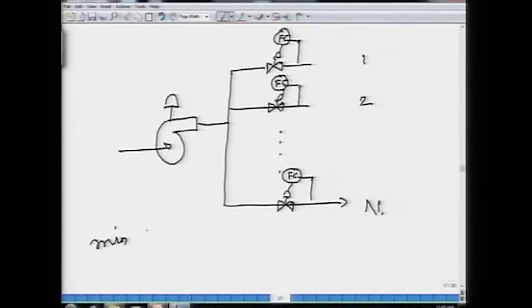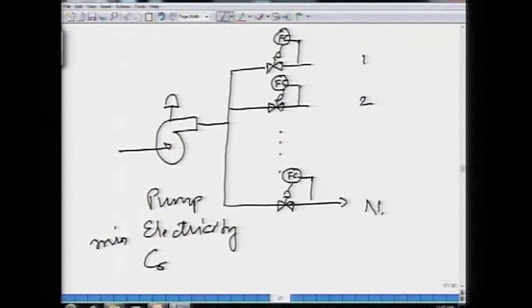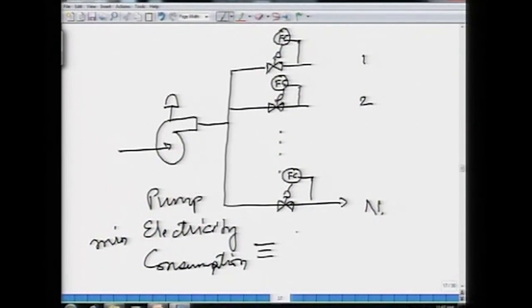Whatever is demanded by each of those processes must be given. This pump, being a big pump, consumes a lot of electricity and electricity is expensive. So while meeting the demand of all the processes, I would like to minimize the RPM at which this pump is rotating — that is, minimize pump electricity consumption — which is equivalent to operating the pump at the minimum possible RPM.